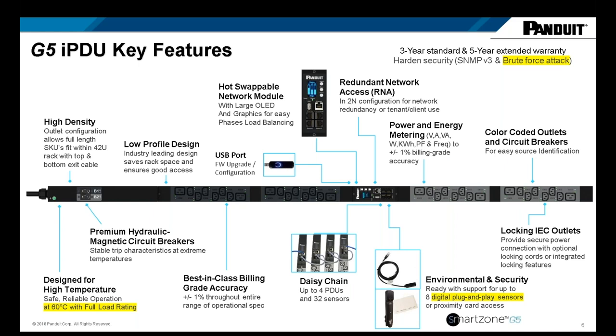This also let us increase sensor accuracy and put multiple sensors on a single bus. Why is that important? According to ASHRAE, the front of the cabinet should have 3 temperature points plus a humidity probe—4 sensing points in front—plus a temperature probe in the rear. By going digital, we're able to put all 4 of those sensing ports into a single part number, which we call the 3T plus H.